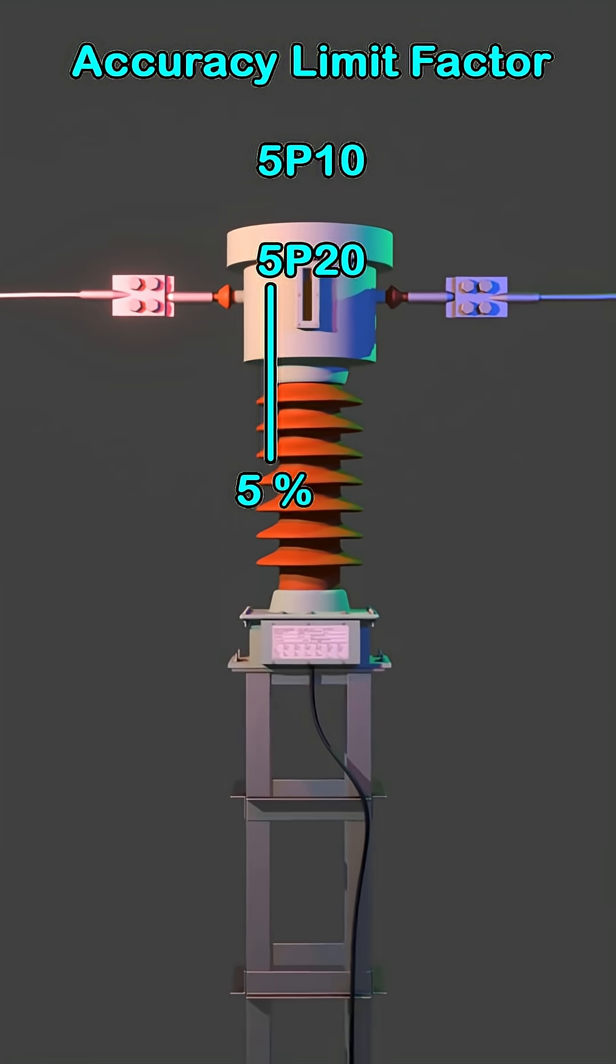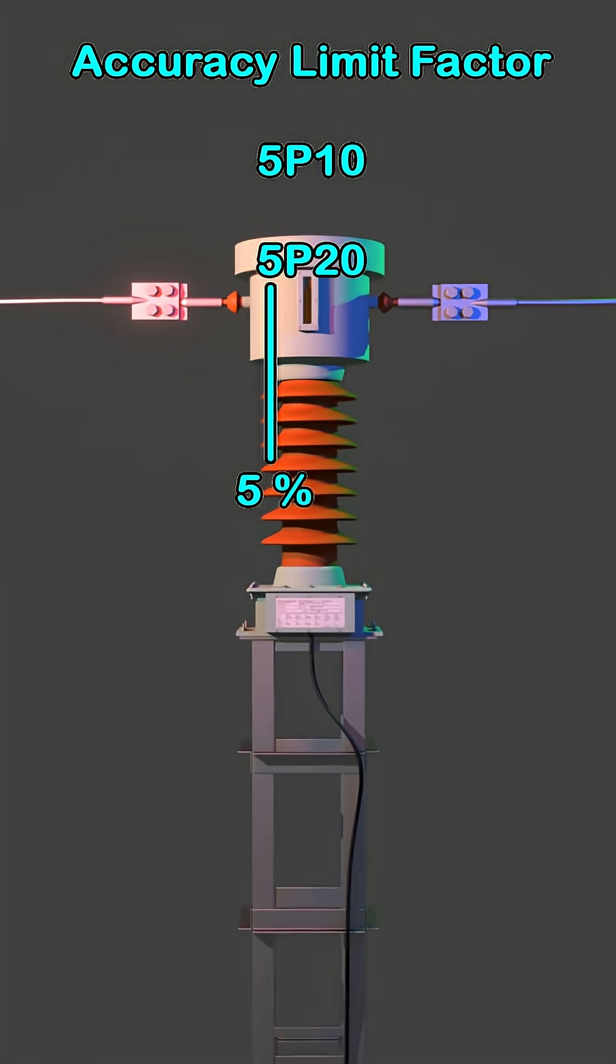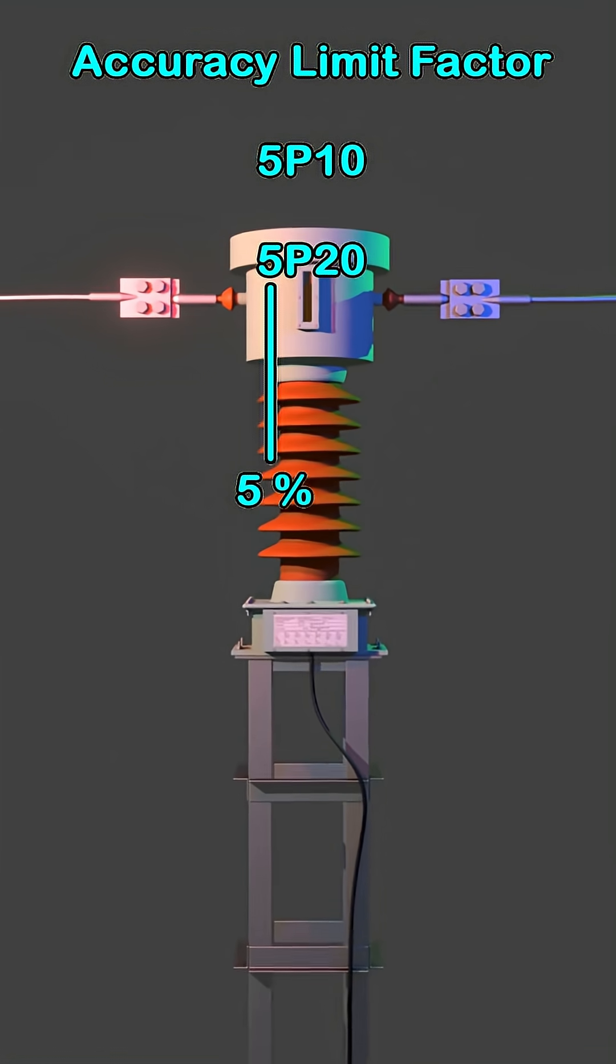The 20 times the rated primary current means the rated primary current multiplied by ALF, which gives the accuracy limit current.